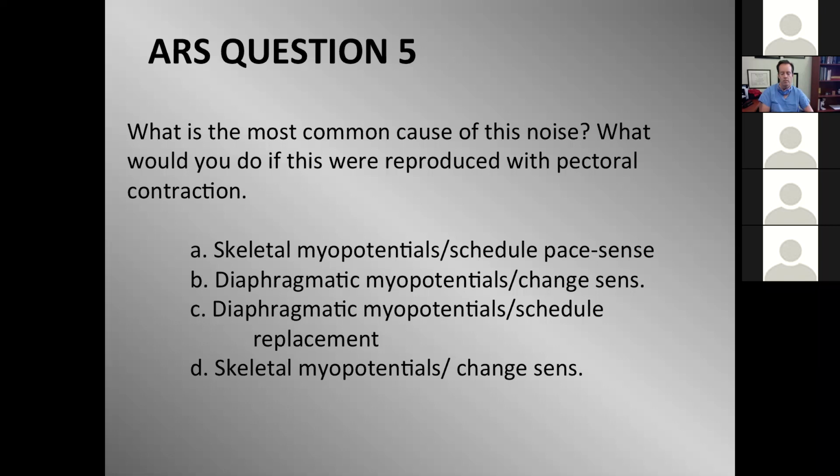Okay, Jeremy. Thanks. If you notice noise on a patient's pace sense conductor, is there ever a role for reprogramming them from dedicated to integrated bipolar, or do we have to consider that the risk of conductor fracture for the high voltage lead wire is also too high, and you wouldn't expose the patient to that? What kind of noise are you referring to?